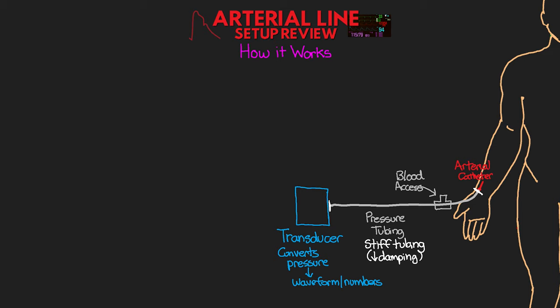And so this is the piece that converts the pressure in the tubing into the waveform and numbers that we see on our monitor. Now, just below the transducer, so between it and the end of the tubing or where the patient will be, is a three-way stopcock. And this stopcock here is how we're going to zero our transducer. Now, on the transducer is going to be a flush whip or a fast flush activator.